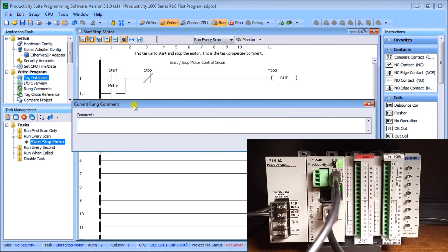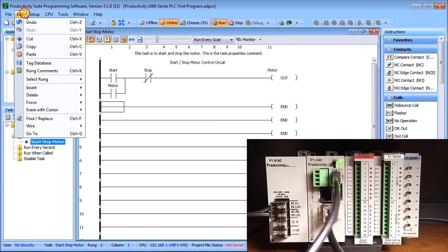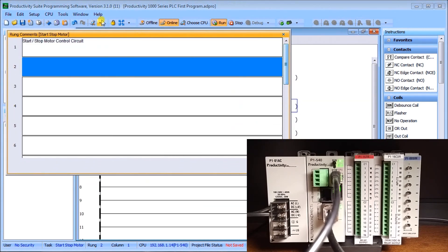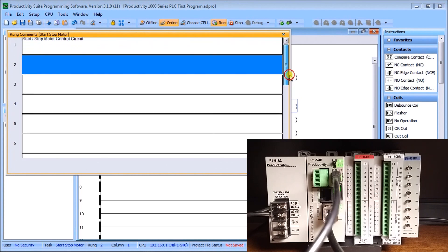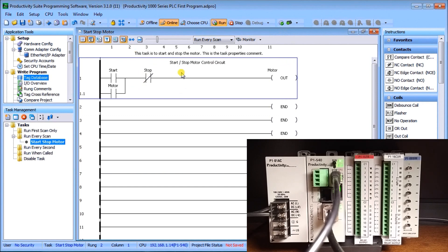Double-clicking the top of any rung opens the rung comment editor directly — a quick and easy method, as long as the Rung Comment icon is highlighted. To see all rung comments at once, go to Edit then Rung Comments, or use the shortcut Ctrl+K. This opens a window showing all rung comments within the Start Stop Motor task. You can double-click on any entry to add, remove, or modify notes on that particular rung. Close it with the X in the upper right corner.